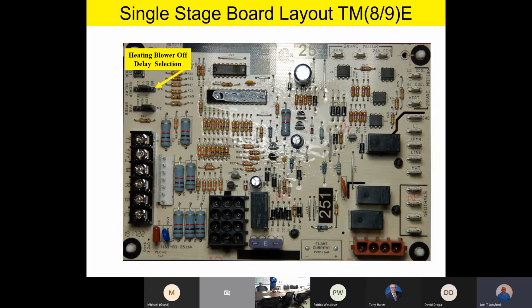Right above that, we have another jumper selection, and this is our blower off delay function. What this does is allow you to field select how long the fan continues to run after the call for heat is terminated. It normally comes from the factory at 120 seconds. However, it is field selectable from 60 to 180 seconds. Basically, once the call for heat goes away, how long does the fan continue to run before it shuts off? That's what we call our heating blower off delay function, and that is field selectable from 60 to 180 seconds. Any questions or comments on those 2 jumper selections before we continue?